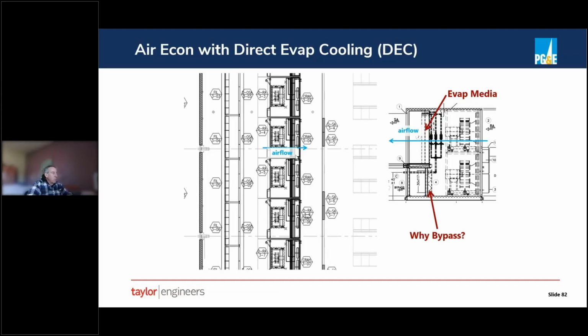And so the air didn't mix. What's happening is we would have a band of hot air coming out at the low elevation with a band of cold air at the higher elevation. And so the servers that were on the bottom of the racks were seeing hot air. The servers at the top of the racks are seeing cold air. And that's not acceptable. You need to basically have the environmental criteria met for all the servers. So I won't get into how we solved this problem, but we ended up coming up with a fix.